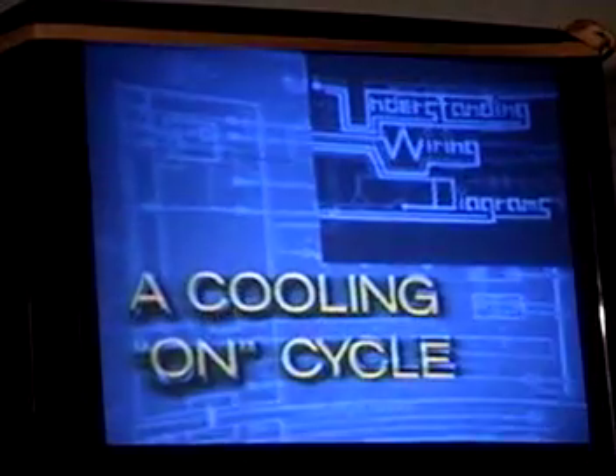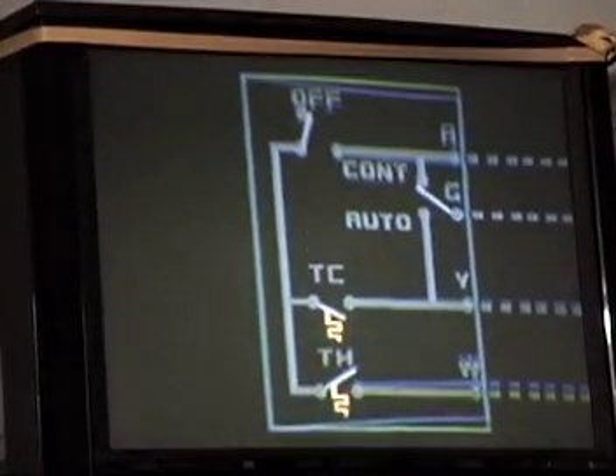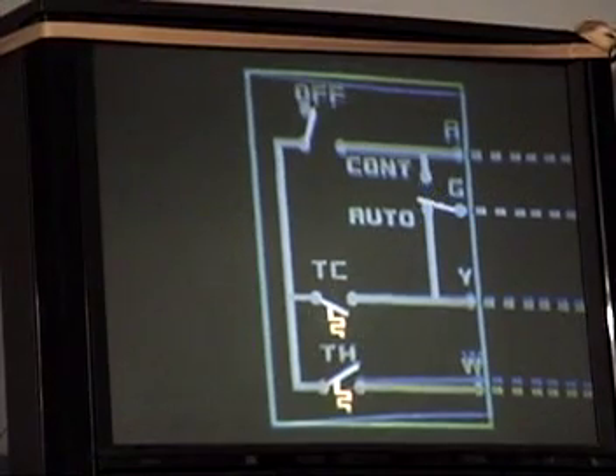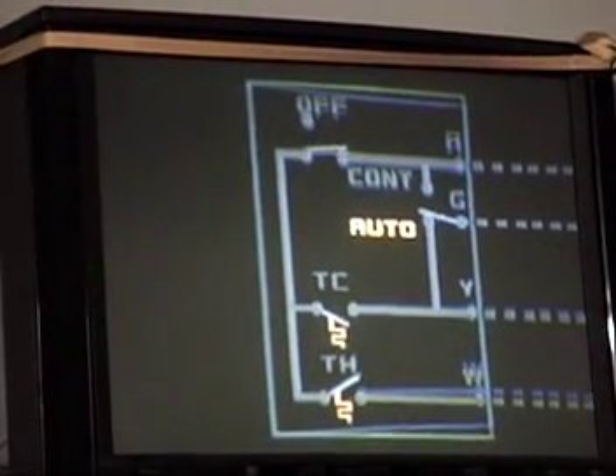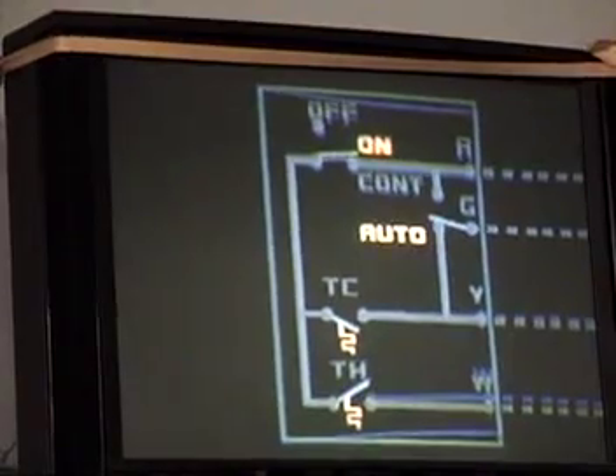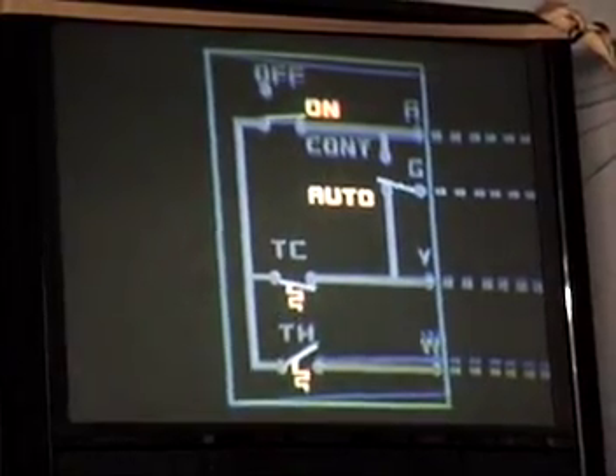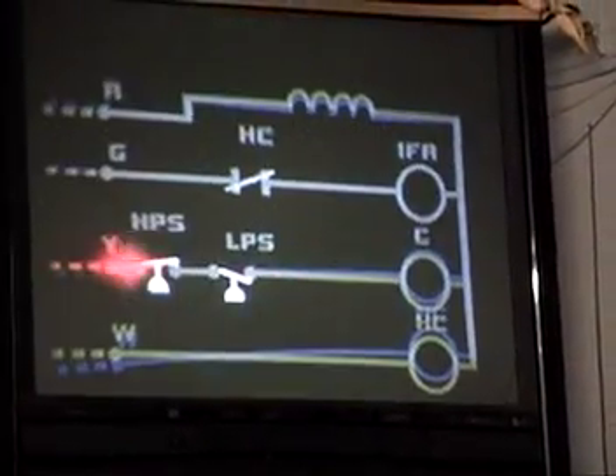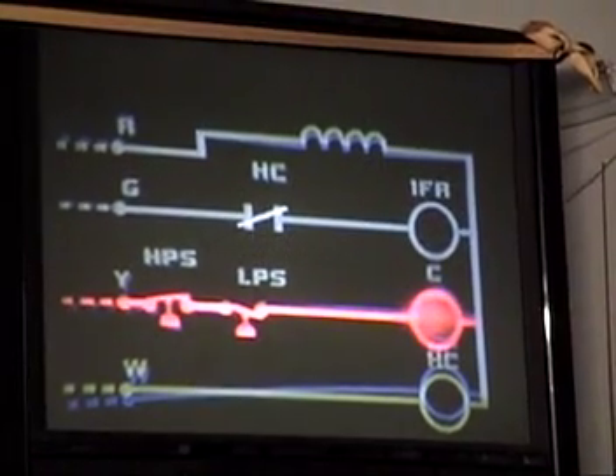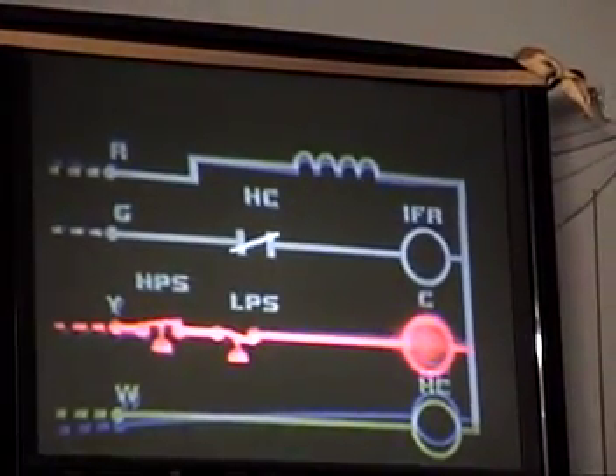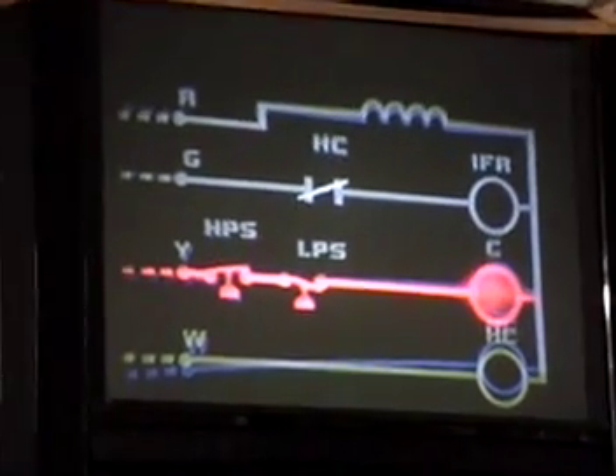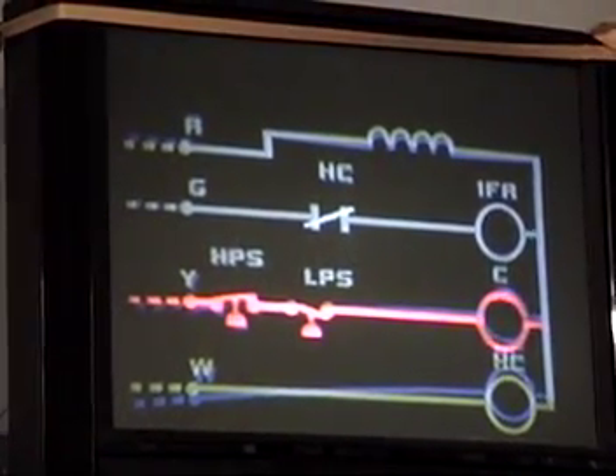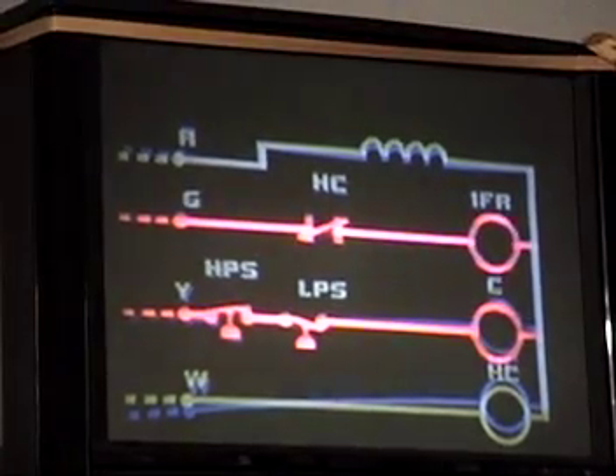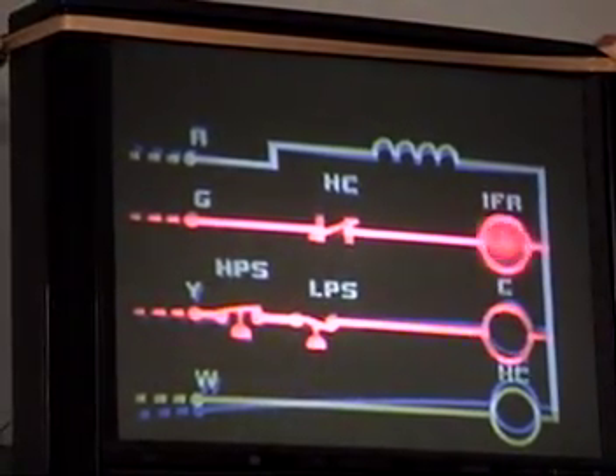Let's discuss the start of a cooling on cycle. We're going to set the fan switch at auto and have the thermostat switch set to on. Now, when the room temperature rises to the thermostat setting, the TC switch will close and there'll be flow to Y and the safety controls. If the system pressures are normal and both switches are closed, the contactor will energize. At the same time, a parallel circuit will energize the indoor fan relay through the fan switch G and the normally closed contacts of the heating contactor.